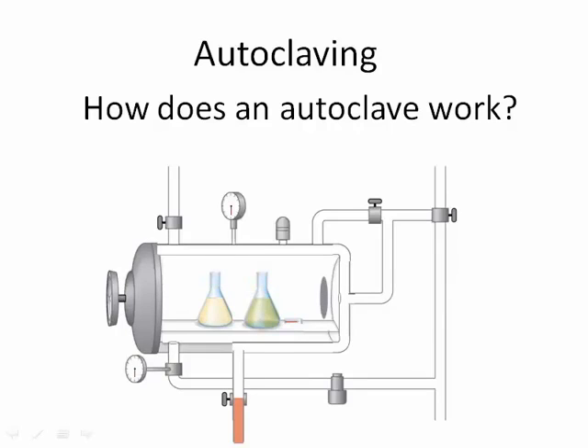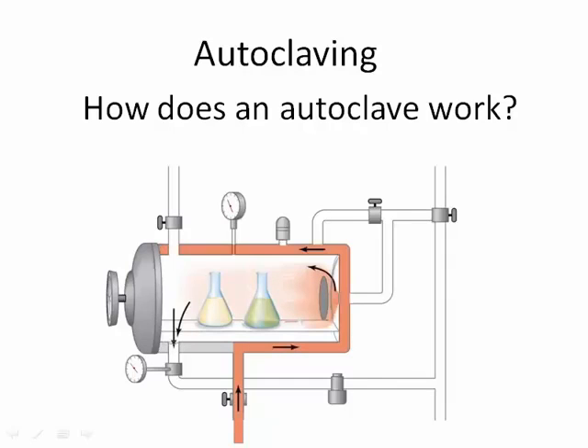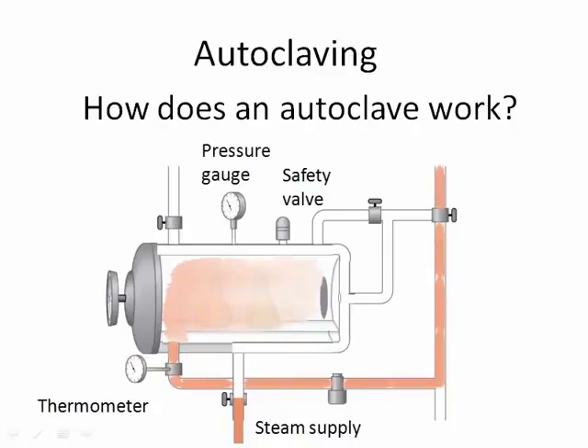A valve is opened and steam floods the chamber, driving the air, which is heavier than steam, out the drain. The entire chamber fills with steam. Once air is driven out and the pressure has reached 15 pounds per square inch, it takes about 15 minutes to sterilize the objects, depending on their type and volume. Then the steam is evacuated from the chamber through the drain.